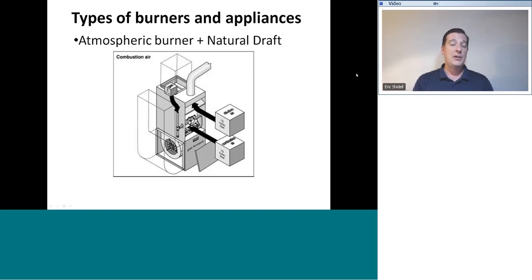This is one reason why natural draft appliances are no longer commonly produced, except in water heaters, and those are probably going to be going away soon too. Natural draft appliances have an opening at the top to allow this dilution air to come in, and I'll get to the reason why dilution air is there in a minute. Because the flues are constantly under a negative pressure and they're constantly sucking, they are constantly drawing in air up the flue pipe. That air, if it's in the conditioned space, has already been paid to be heated, and it's going to be drawn right up the flue at all times. And that is a condition that we would like to stop, as it leads to an inefficient, energy wasting structure.